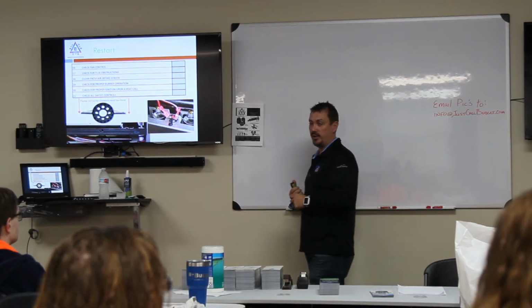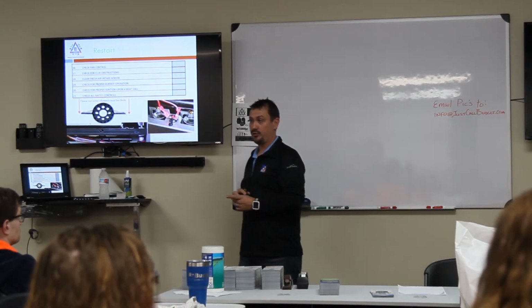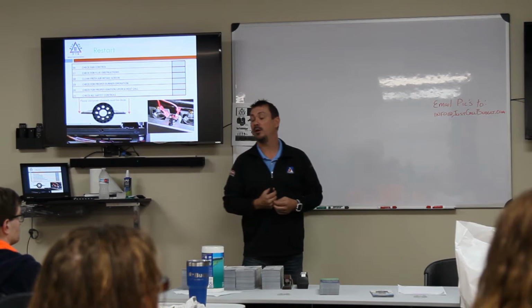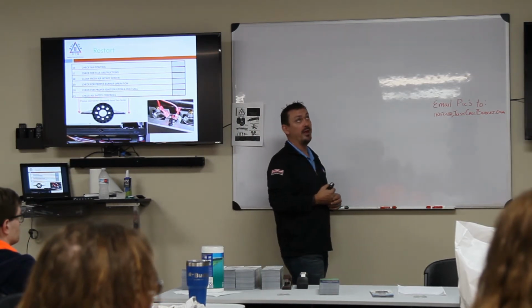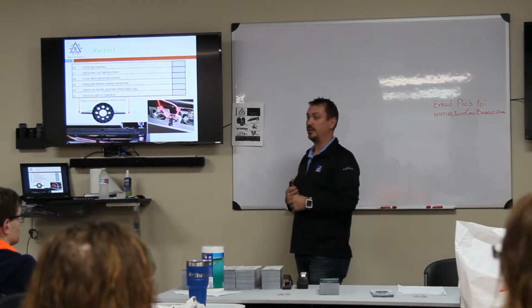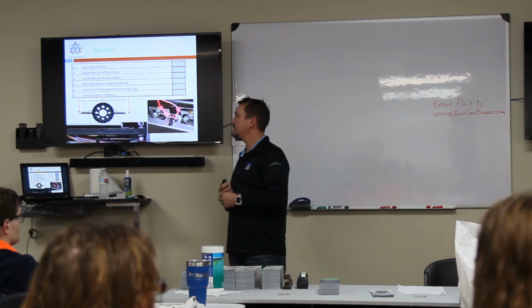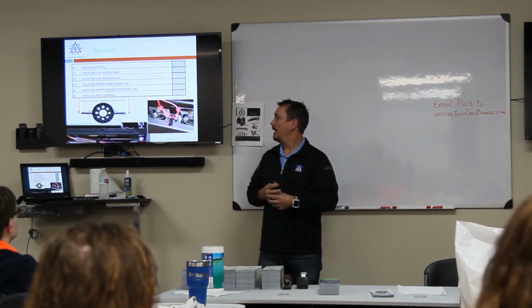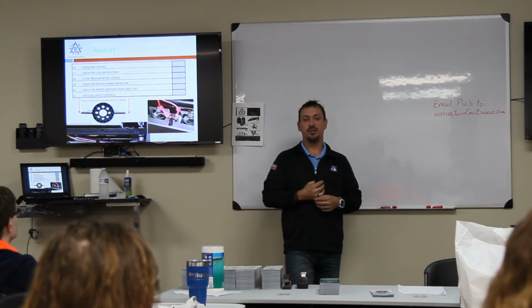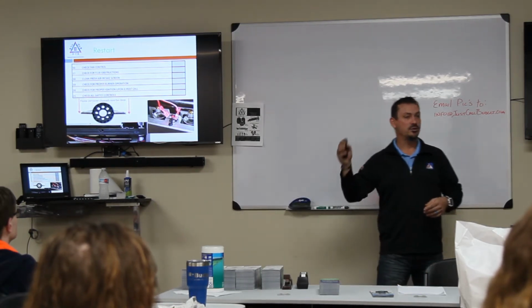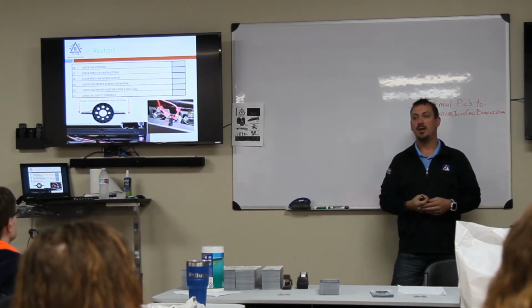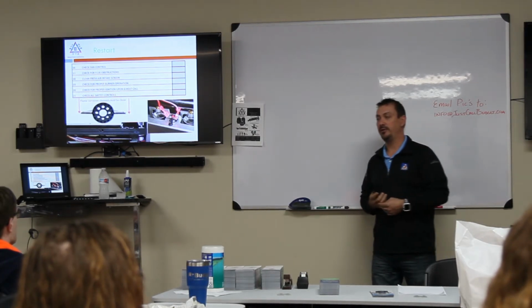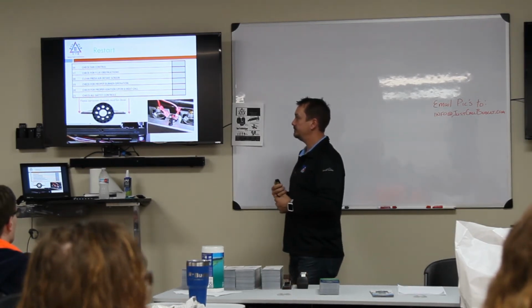Checking your flue for obstructions. Again, this is checking with the pressure switch on, checking the pressure switch with an inducer with a dual port digital manometer or a magnehelic, which will make sure and ensure that your flue is nice and clear and free from obstructions. And then checking the ignition sequence is proper, making sure again that there's no delay from the hot surface igniter all the way over to the flame sensor.